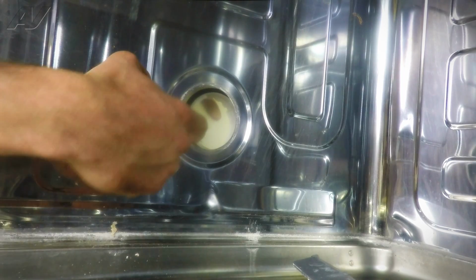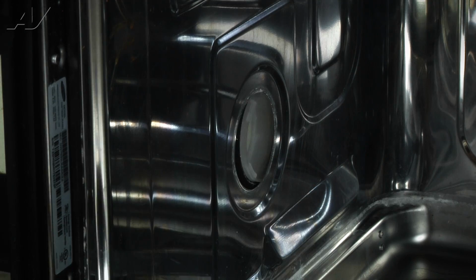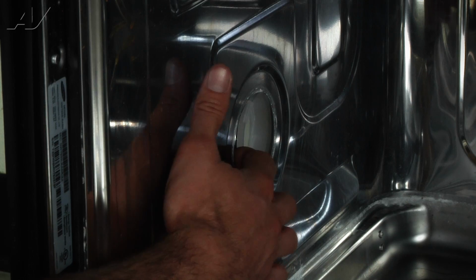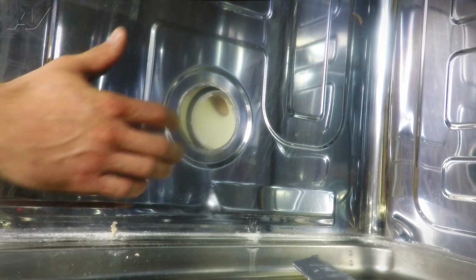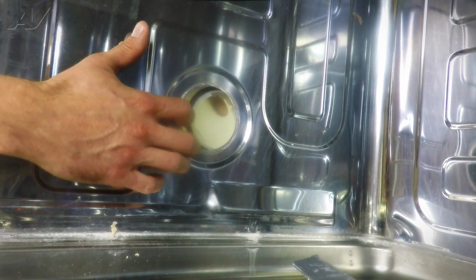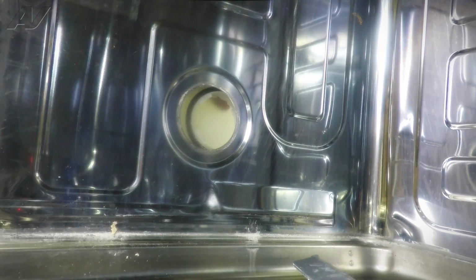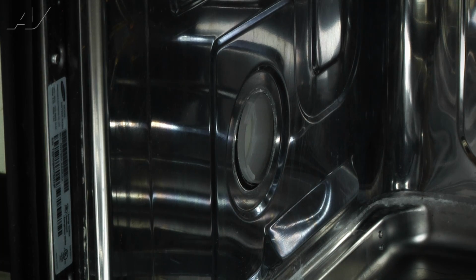Now you want to take note, you can see right there, that's a gasket. If that thing falls off when you put this back together, the unit will leak. So you want to make sure that you keep that gasket there and that it is in place when you reinstall it.